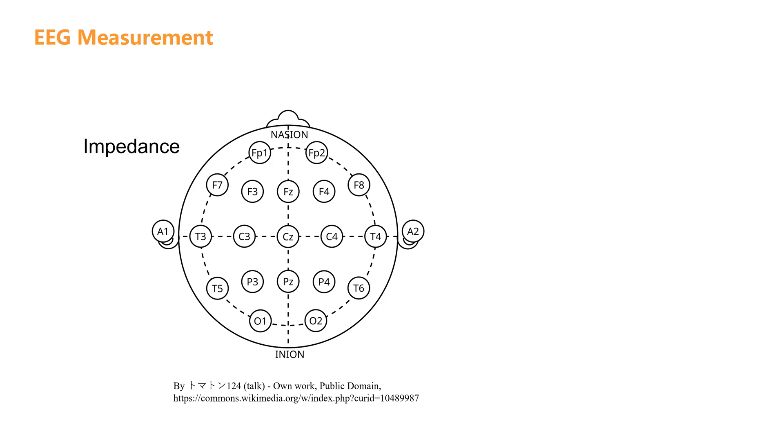Now, let's explain impedance. EEG impedance refers to the resistance between the electrodes and the scalp, and it is an important factor that affects the quality of EEG signals. The magnitude of the impedance can influence the efficiency and quality of signal transmission.